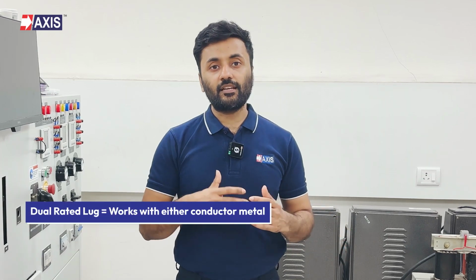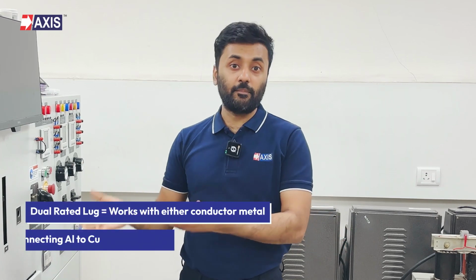In a solar plant, aluminium cables from the string inverter connect to a copper busbar inside the combiner box. The cable is aluminium, the busbar is copper, two different metals need to join. This is where you use a bimetallic lug. So if you need one lug that works with either conductor metal, use a dual-rated lug. If you need to connect aluminium to copper, use a bimetallic lug.